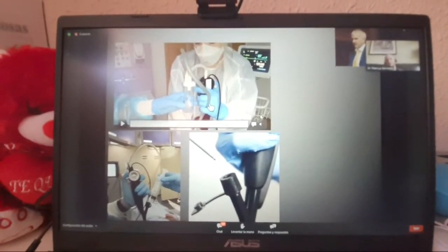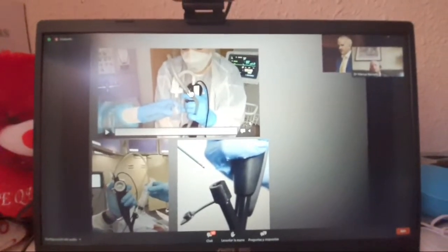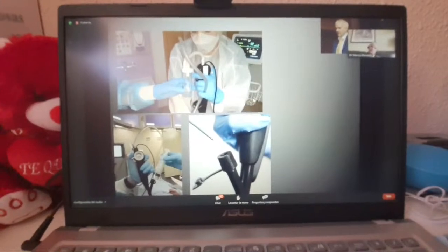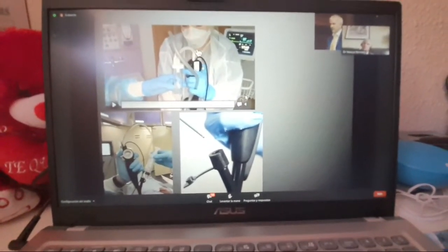So you can see in this image, our respiratory fellow or registrar is holding the tubing coming out of the trap in a loop to stop kinking of the tube between the trap and the scope. People aren't aware of this, and they're wondering why their lavage is not good enough.